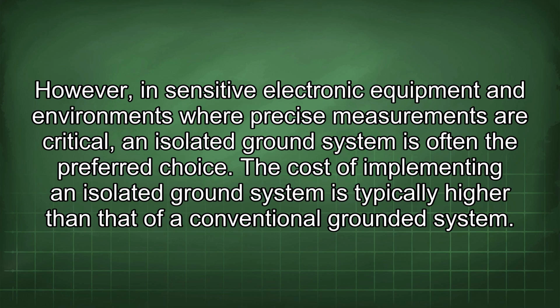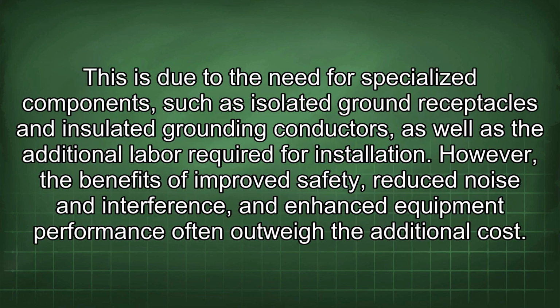choice. The cost of implementing an isolated ground system is typically higher than that of a conventional grounded system. This is due to the need for specialized components such as isolated ground receptacles and insulated grounding conductors, as well as the additional labor required for installation. However, the benefits of improved safety, reduced noise and interference, and enhanced equipment performance often outweigh the additional cost.